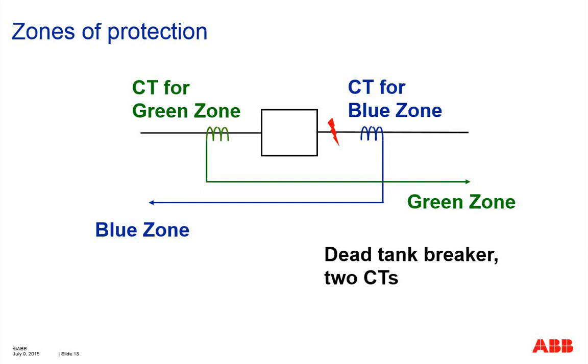It's no problem. However, remember I mentioned before that for this type of bus configuration, sometimes the substation will operate with this tiebreaker normally open. It's not closed, it's open. So when you operate a main-tie-main scheme with the breaker normally open, and a fault occurs as indicated here between the blue CT and the open breaker, in this case the blue zone will operate.